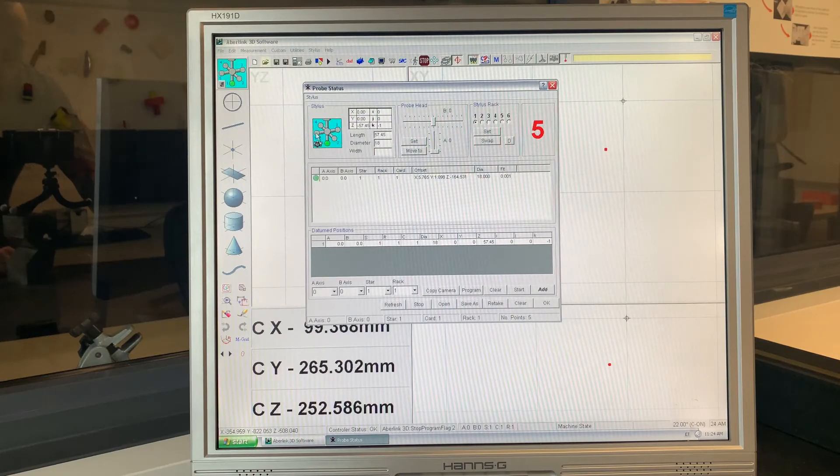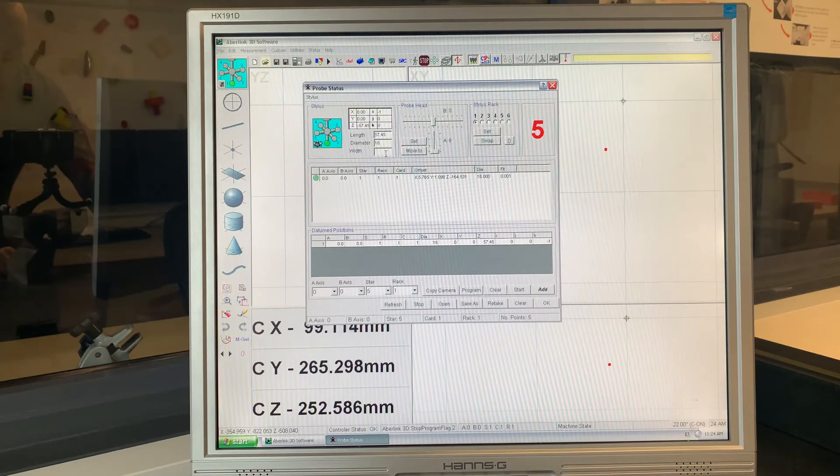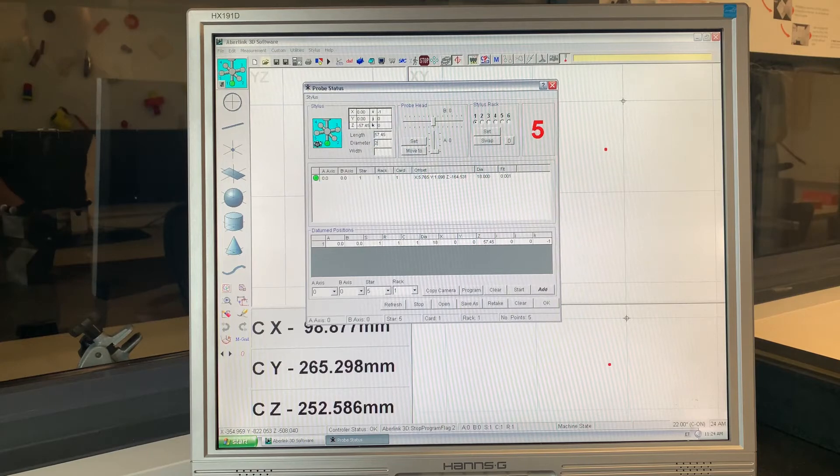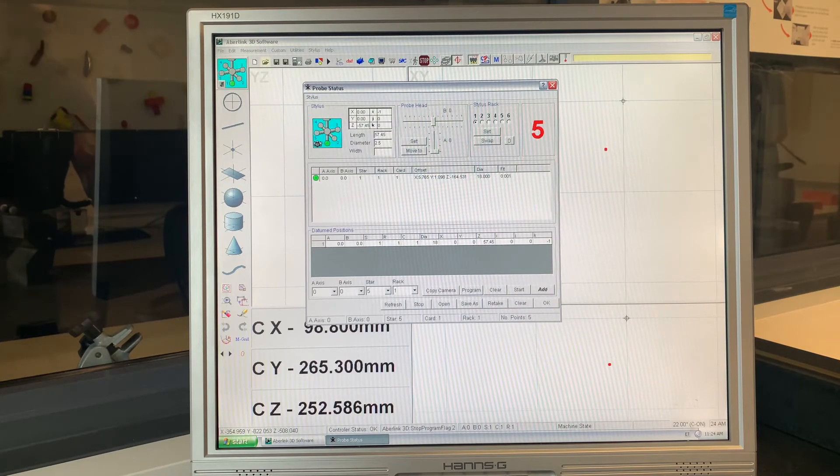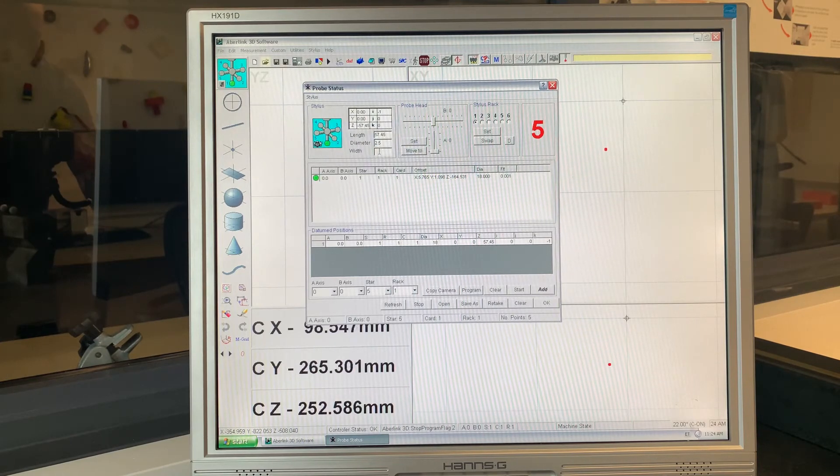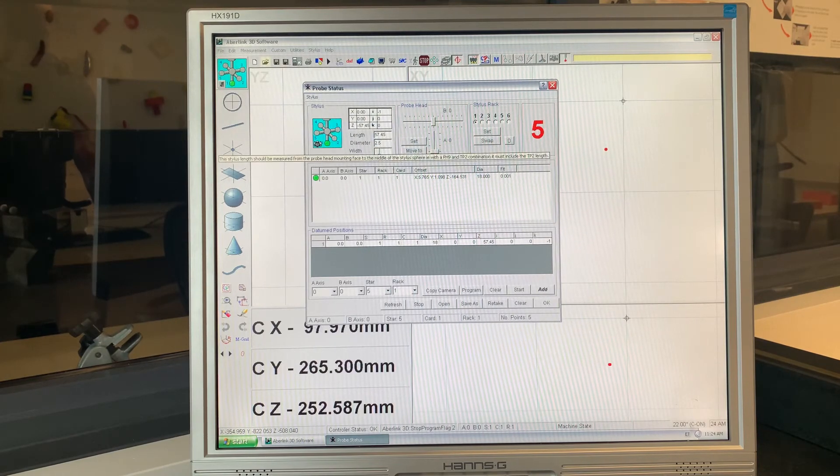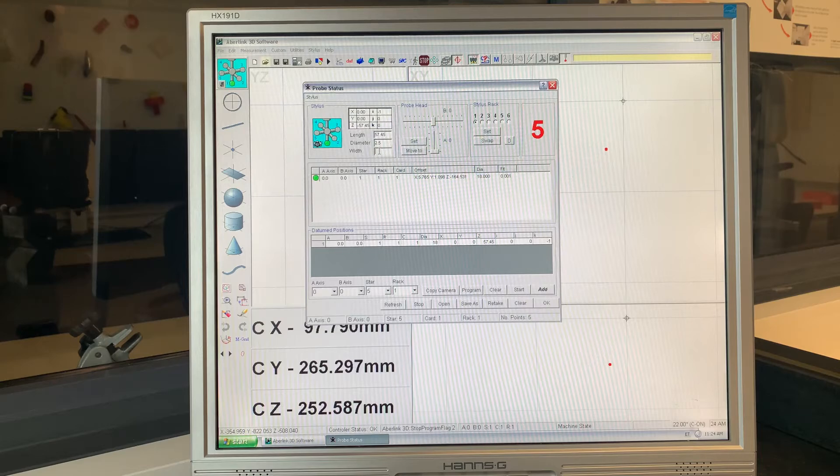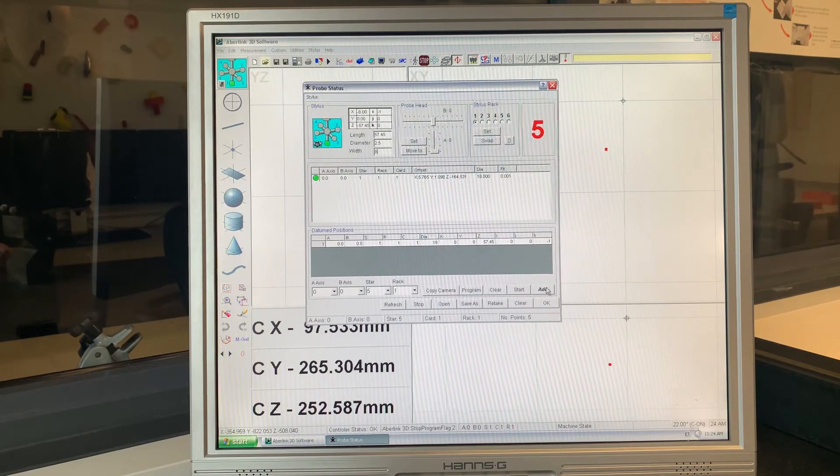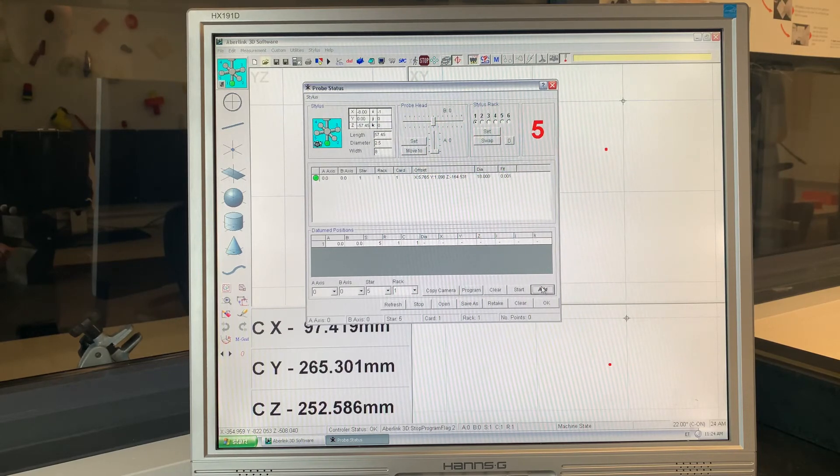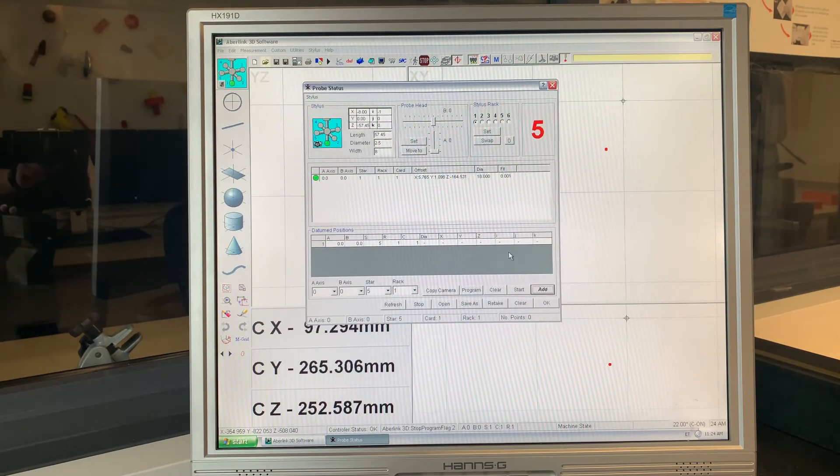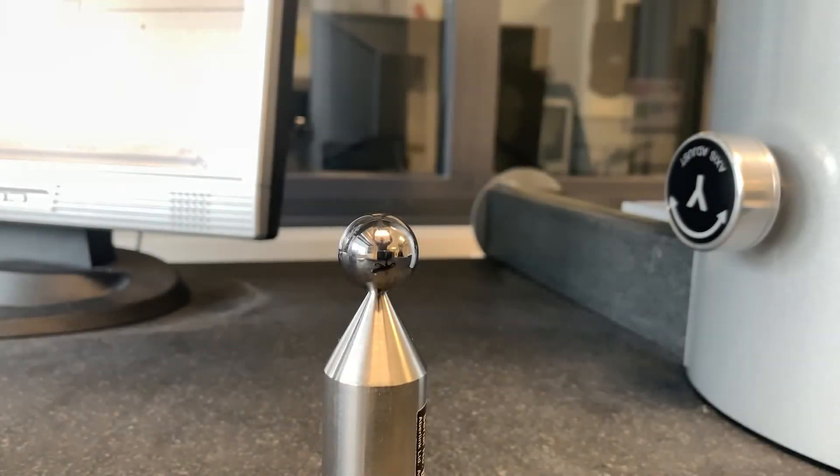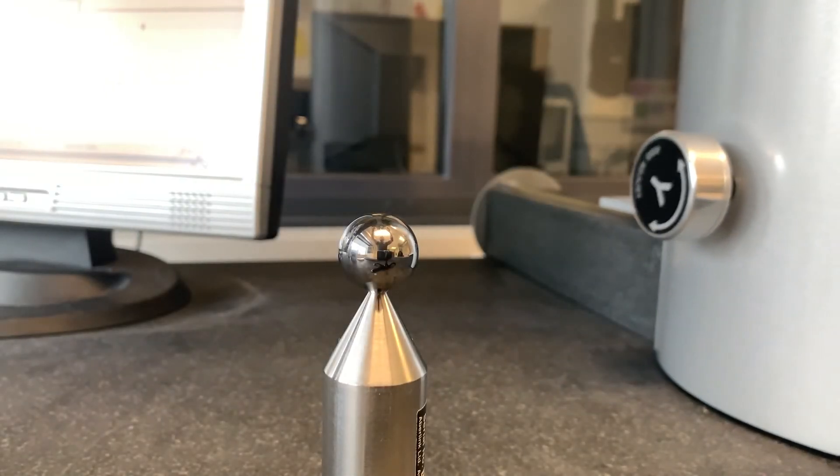Select stylus position 2. Edit the ball diameter on stylus position 2 so it matches the length previously measured. Click on the add button and take about 10 points using the spherical form on the bottom of the roller.